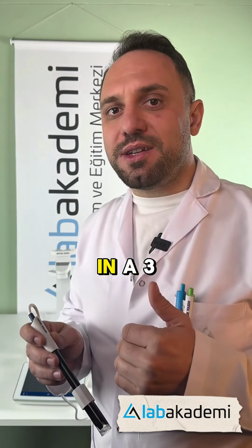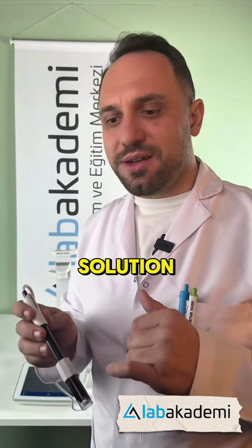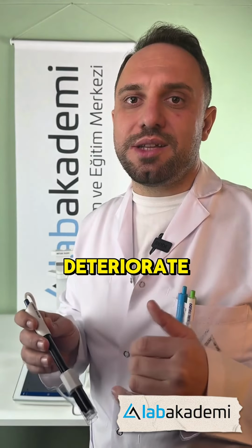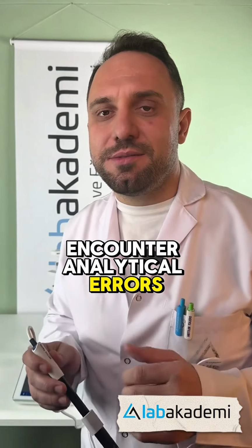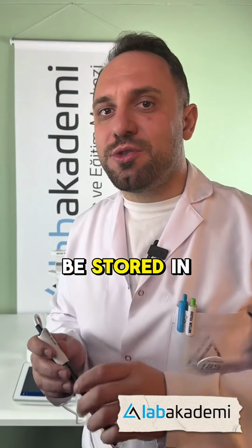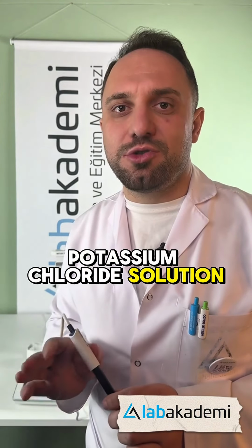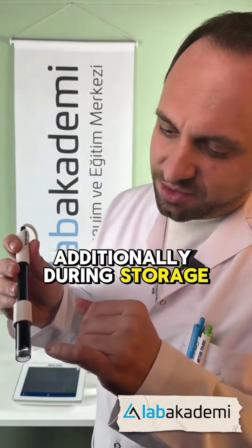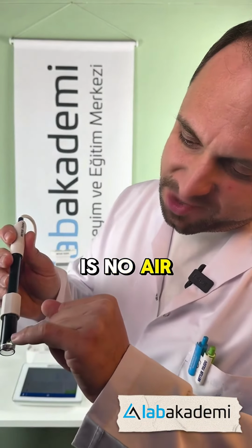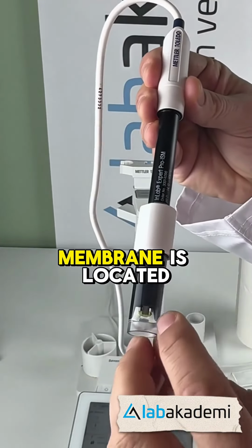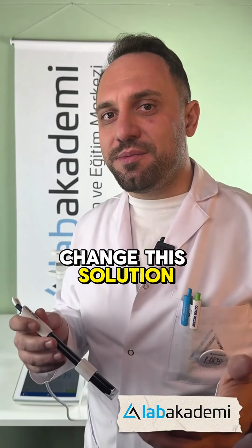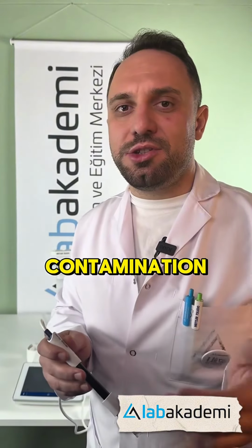If we do not store it in a 3 molar potassium chloride solution, the permeability of the membrane will deteriorate and we will encounter analytical errors. Therefore, it must always be stored in a 3 molar potassium chloride solution. Additionally, during storage, we need to ensure that there is no air bubble, especially in the part where the membrane is located within the solution. And we should change this solution frequently to prevent contamination.